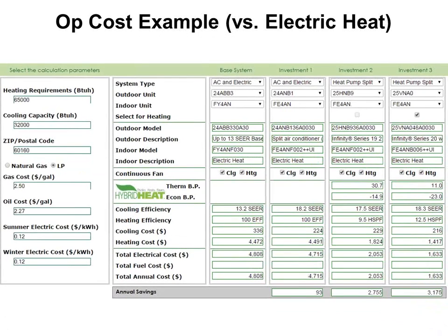Last example, electric heat. If you don't have any gas system at all and you're running electric heat, now your fuel sources are the same. Electric heater uses electric, heat pump uses electric, right? If electric heater is 100% efficient, and the heat pump is 200, 300, or 400% efficient, the heat pump's always going to win all the time, right?